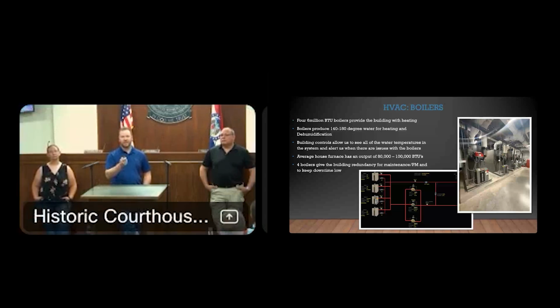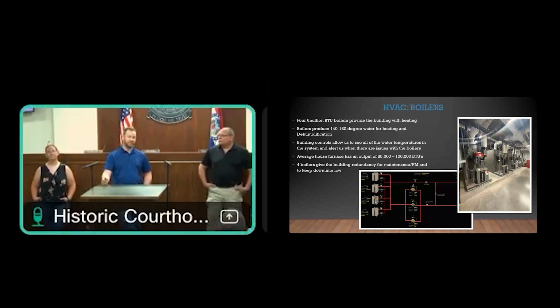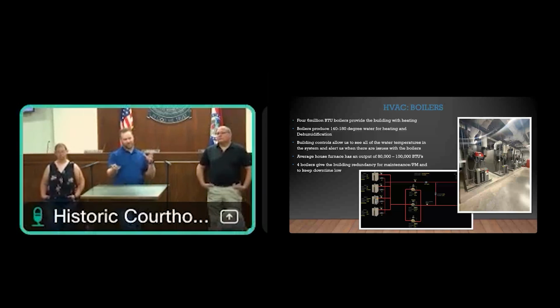And these boilers get PM'd. They get completely torn down. Where you see that red part in the picture is the burn chamber. That gets completely taken out to inspect all the burn chamber. That happens yearly. So that's why it's important to have so many of them, so that we can keep the building warm even when we're doing PMs.